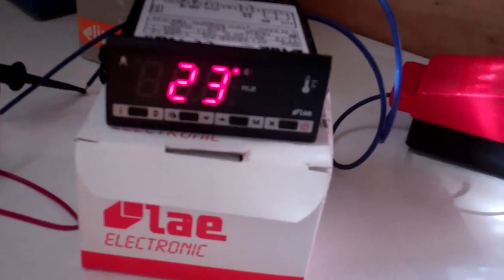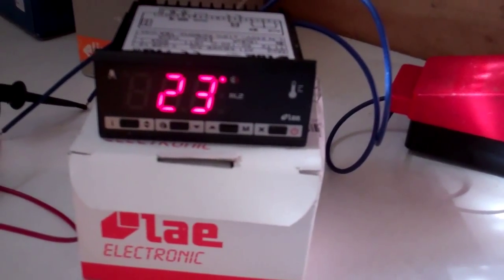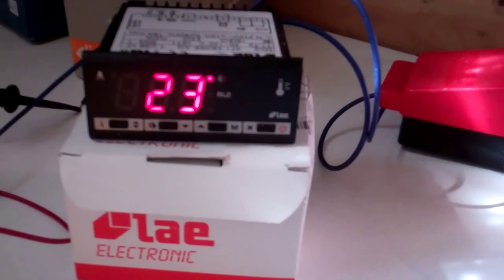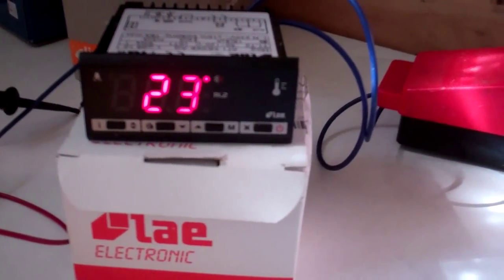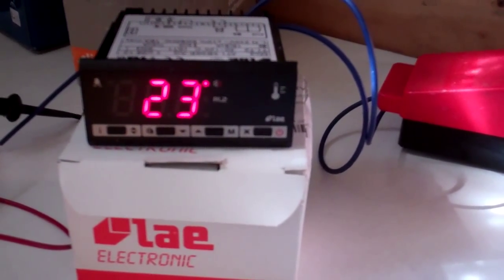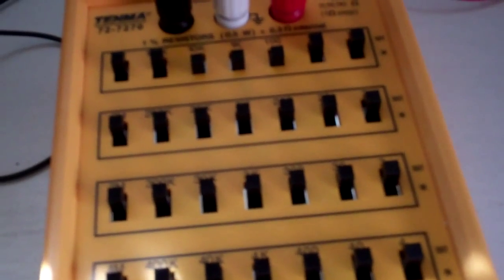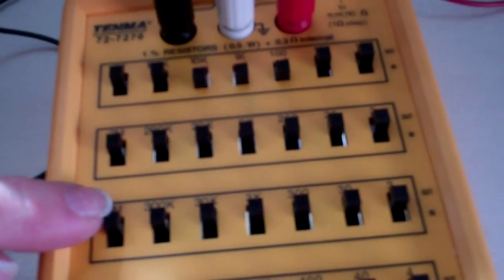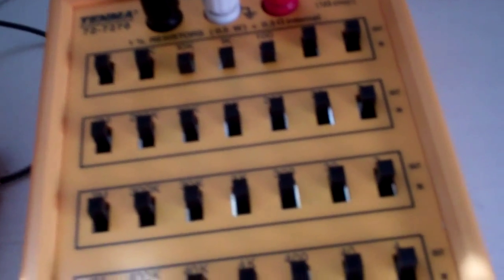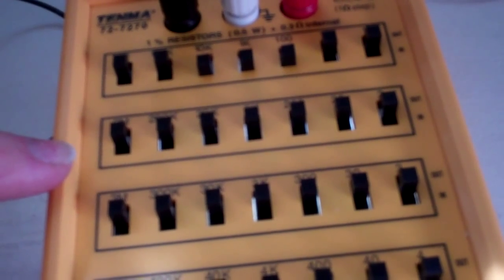I guess if you've got a compressor with a thermistor module on there and you suspect that's playing up you can set the little switches on here to the trip and reset resistances and see if the thermistor module does what it should do. So that would be another useful thing for it.